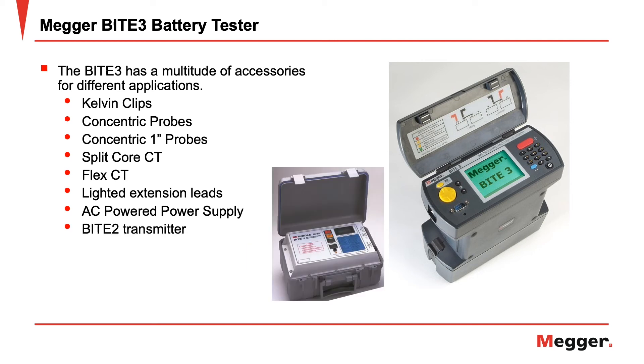The BITE2 transmitter can be used with the BITE3 to test even the largest VLA batteries. It will inject 10 amps of test current through the entire string, allowing for high accuracy and higher repeatability measurements. The BITE2 transmitter will also allow for more precise measurements of intercell connections.